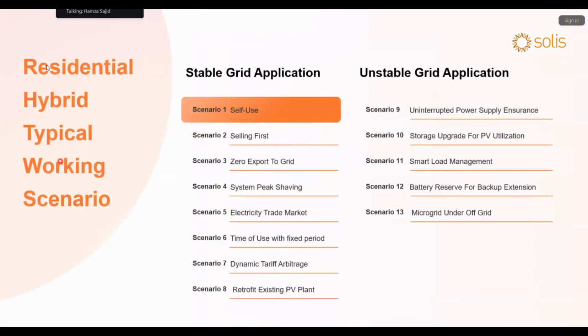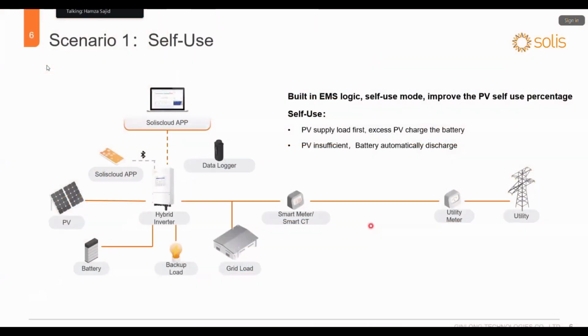Okay, so what are the typical residential working scenarios? First is the self-use. The thinking for self-use is that whatever you produce or store should be utilized, and the priority from the grid should be the least. If the PV is available, the first priority is for the loads, and the second is to charge the battery. And if the PV is insufficient, then the battery will automatically discharge and support the load on the backup side and the grid side. So this is the whole scenario for the self-use.